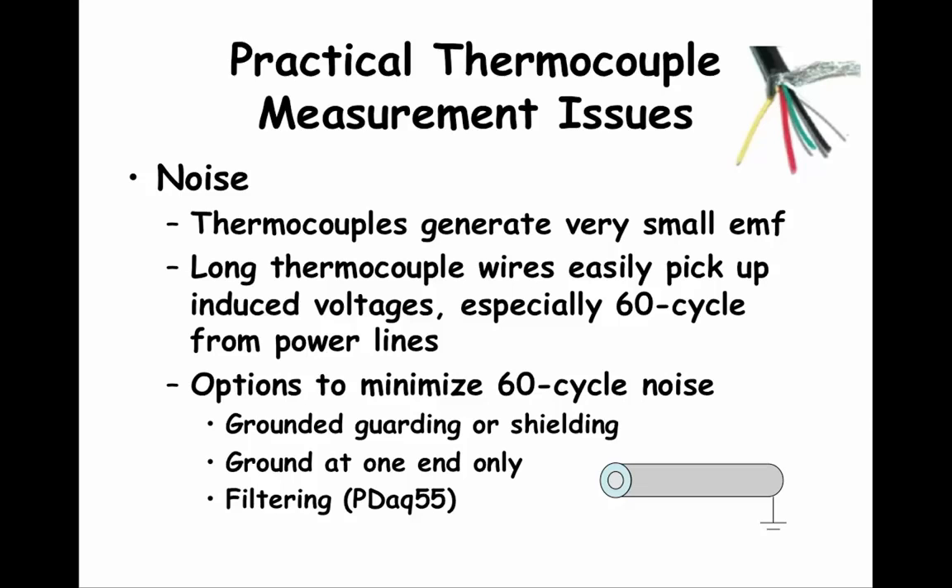It is important to remember that shielded wires should be grounded at only one end. It is usually recommended, if possible, to ground the wires at the recording device. The other method for managing noise — especially 60 cycle noise from power lines in the US and 50 cycle in Europe — is to use a filter. You might remember when we talked about signal conditioning in the PDaq55 that one of the elements was a filter. Filters can mitigate noise, especially 50 and 60 cycle noise. We will talk about filters near the end of class.